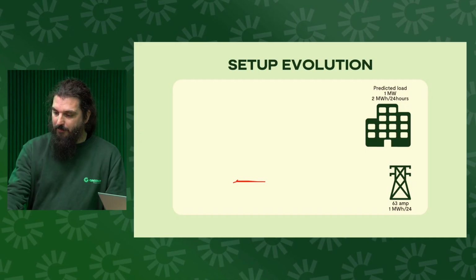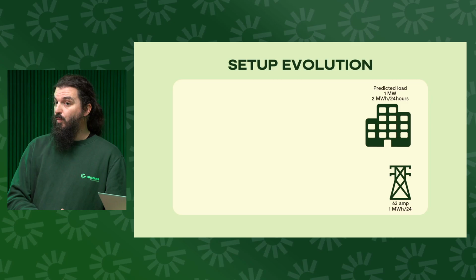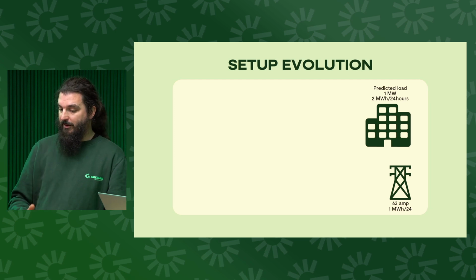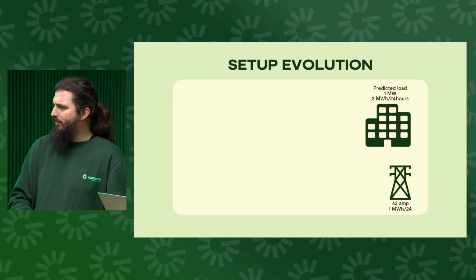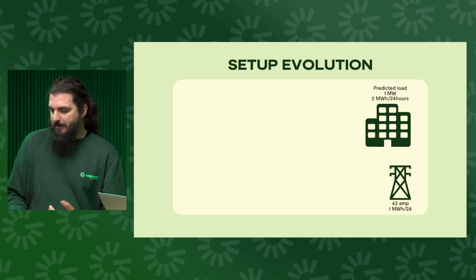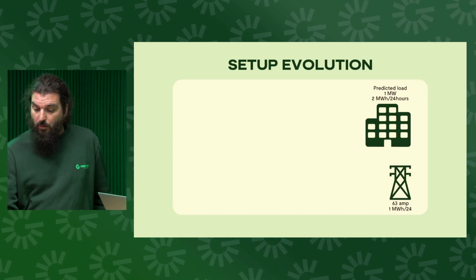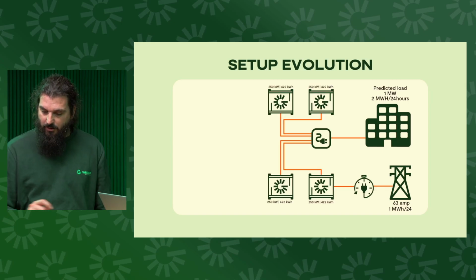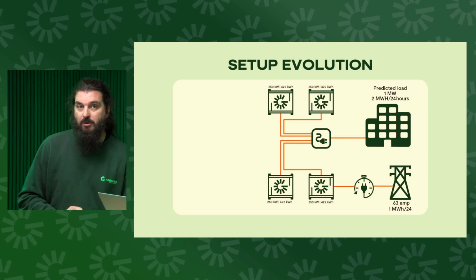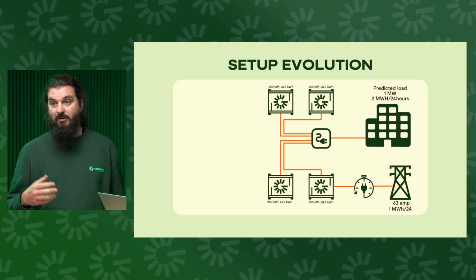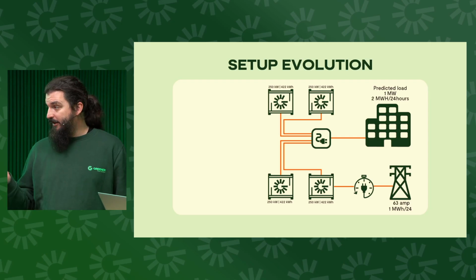So obviously we needed to make sure we could get to the 1 megawatt from that connection. We were not going to do that directly online, because the difference between the 1 megawatt and the 63 amp C connection, or was it 30 kilowatts, is too big. So what we did is we built a little setup with 4 batteries in parallel using our microgrid technology, which is the same frequency driven system as the main national grid, as Dan already talked about. That microgrid, it's the 4 batteries that are now forming the grid.